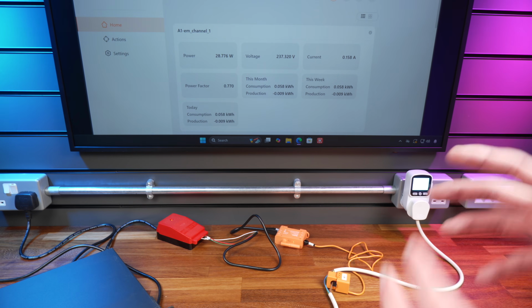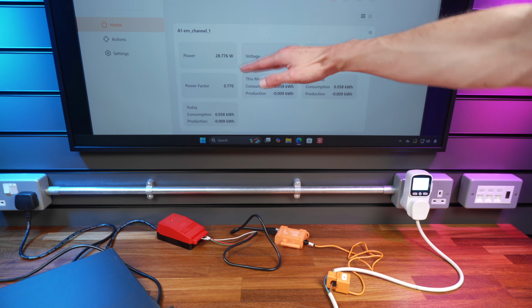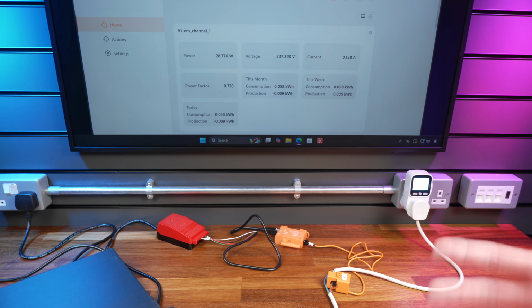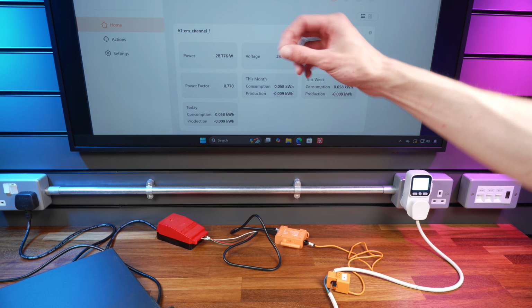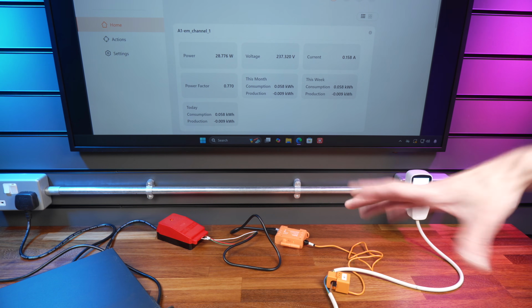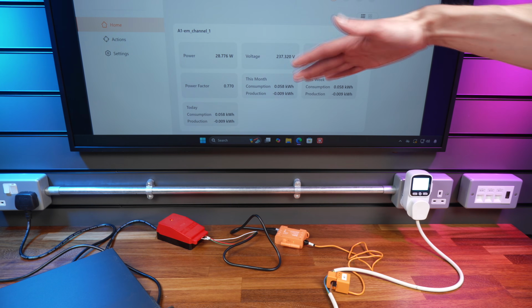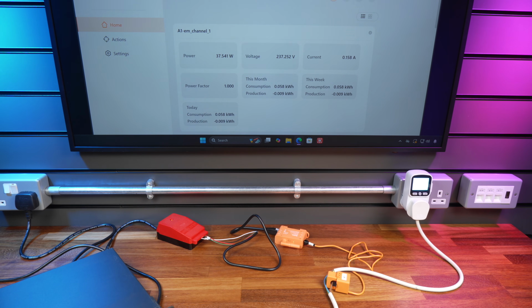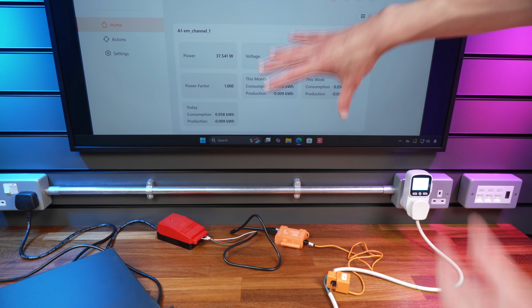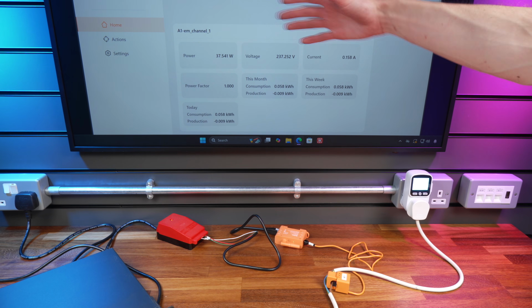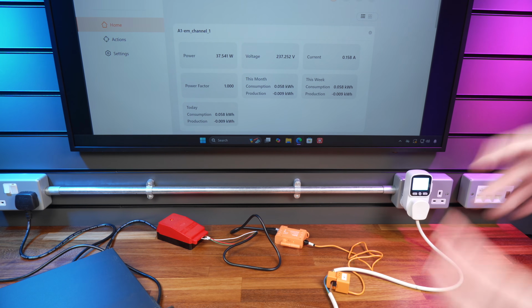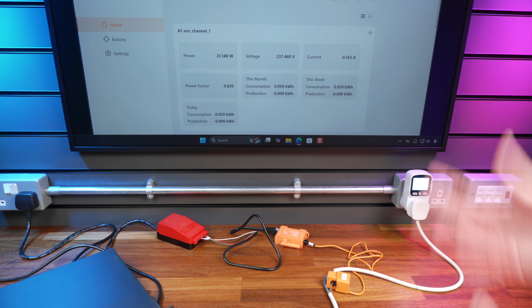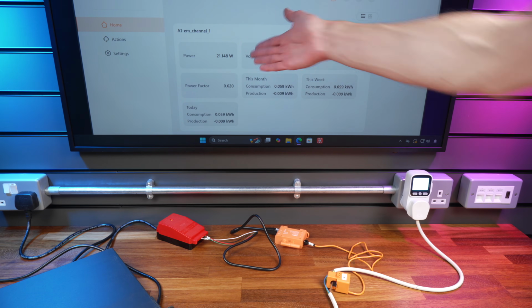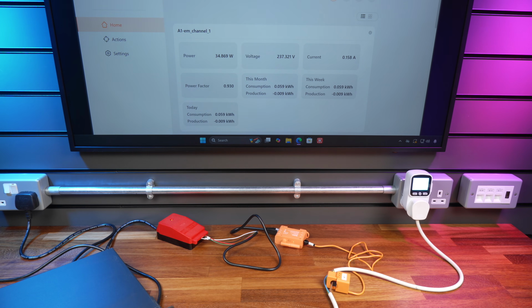And it all seems to have basically the same behaviour, where the minimum power factor value recorded is generally the correct one, but it only seems to record that value periodically, and then in between those times it records a much higher power factor that doesn't really make sense. And of course the issue with this is, if it keeps doing this when it's live, you're going to end up over-reporting your power. You're going to get power values that are too high because it's assuming your power factor is higher than it is. As you can see there, we're now at the correct power factor and correct power level again.